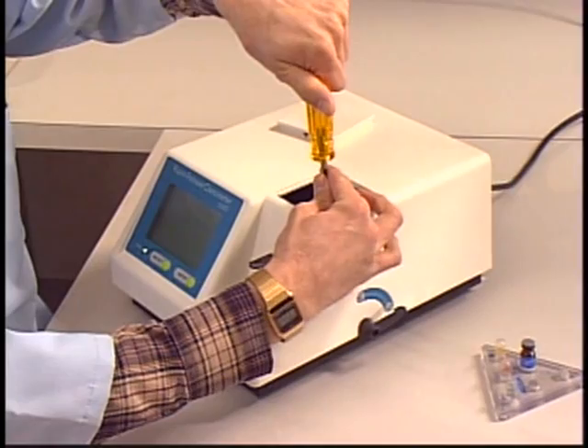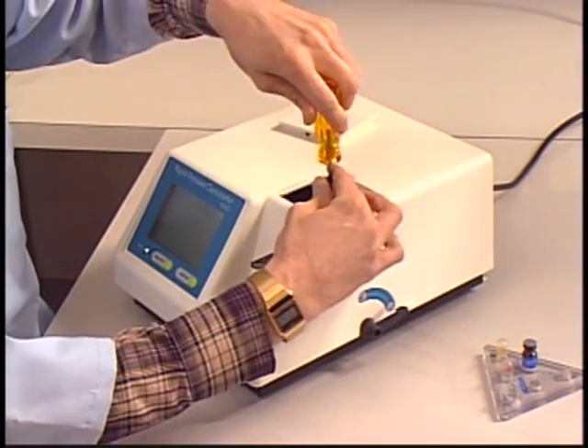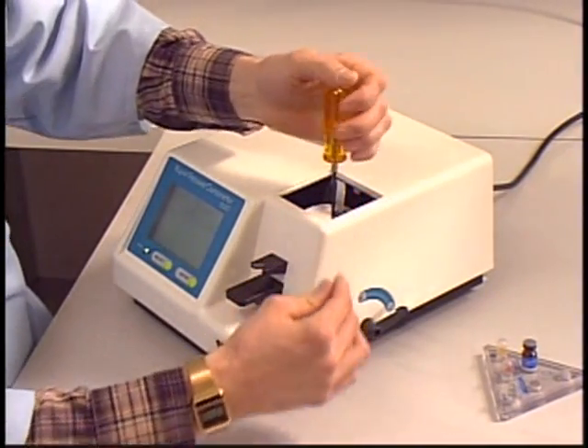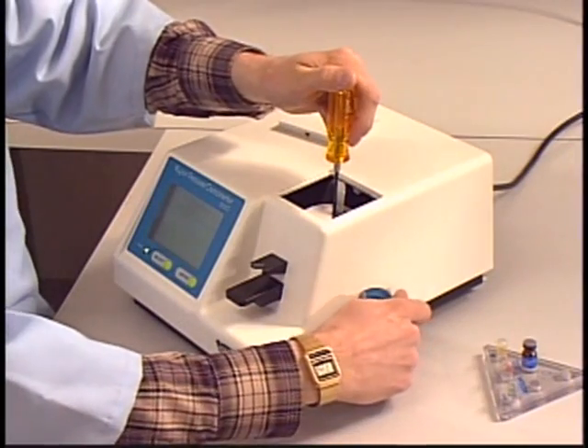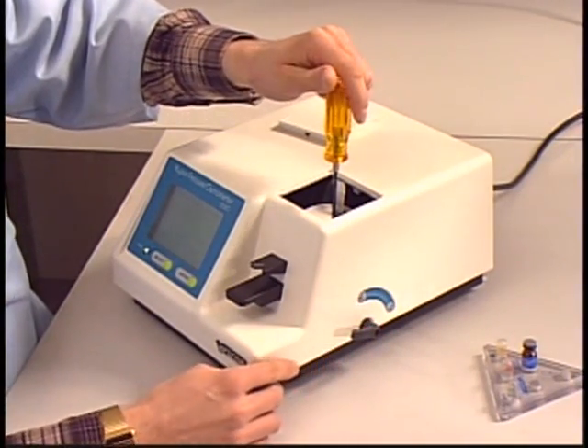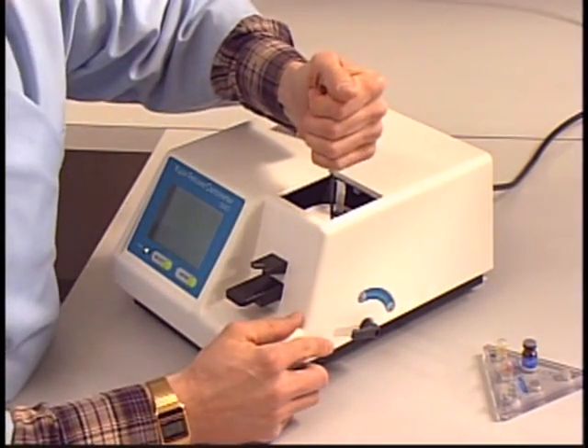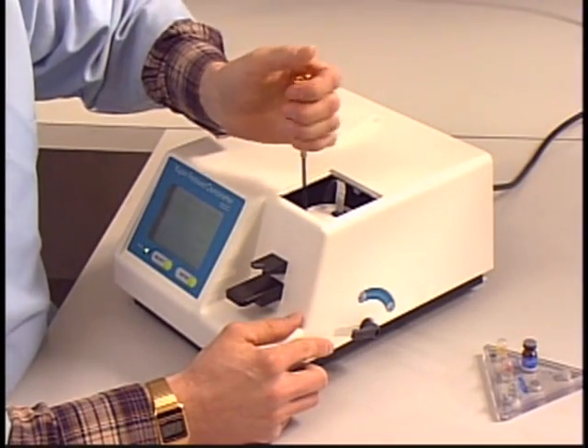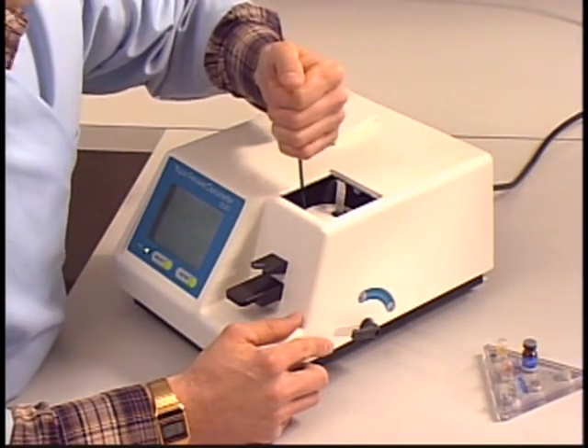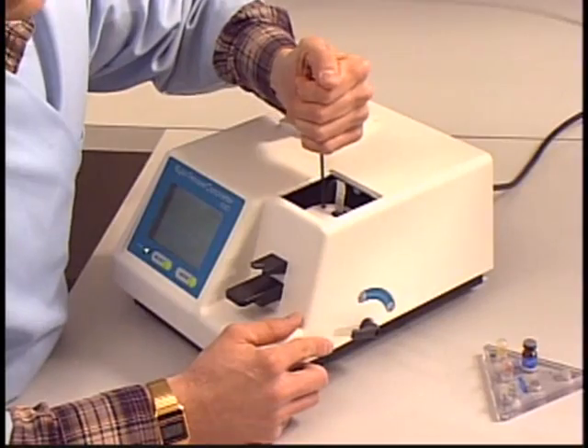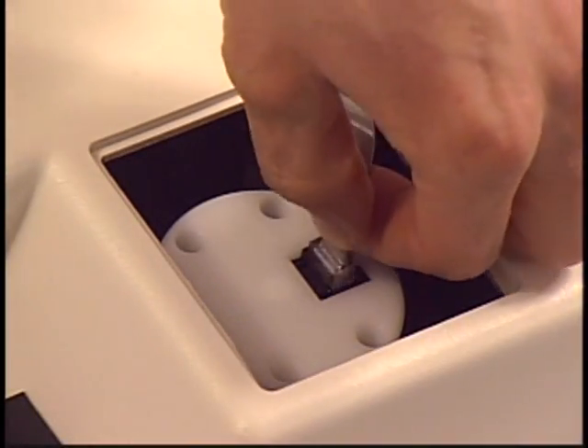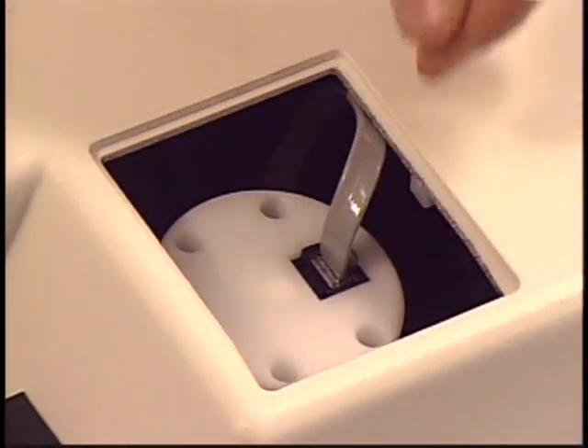Wait a minute, screw that back in. Every once in a while, the problem is simply a loose head. With the chamber locking lever open, check that first. Make sure all 4 screws are firmly tightened. Next, be sure the cable leading to the instrument's head is connected. If the head is tight and the connector secure in its socket, then it's time to clean.